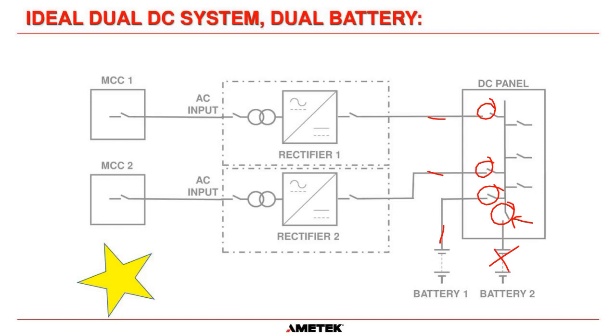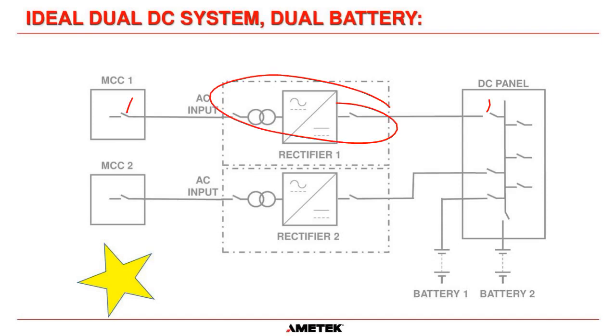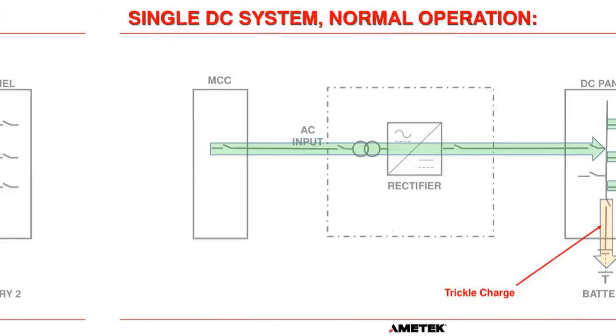So absolutely fantastic way. Obviously it's a bit more expensive, but this is by far the best design of system for your DC critical loads. And I hope you can see why that is from this drawing. Very flexible. You can open this breaker here, open this breaker here, and remove the whole charger. You still have this charger here and the two batteries here. So lots of backup, even if one complete system fails. Very robust way to protect your DC critical loads.